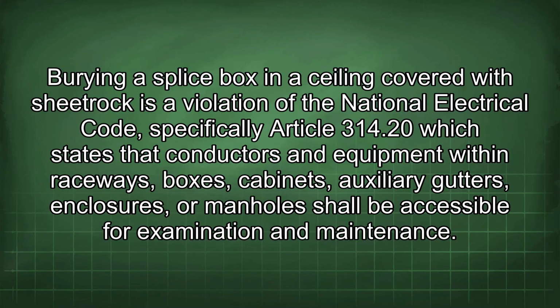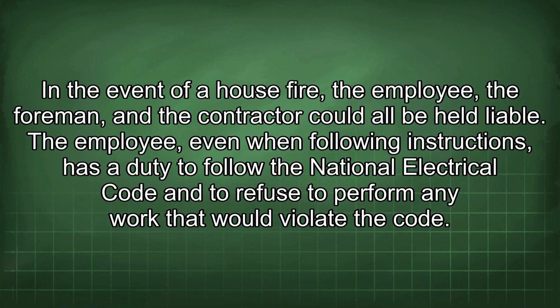Burying a splice box in a ceiling covered with sheetrock is a violation of the National Electrical Code, specifically Article 314.20, which states that conductors and equipment within raceways, boxes, cabinets, auxiliary gutters, enclosures, or manholes shall be accessible for examination and maintenance. In the event of a house fire, the employee, the foreman, and the contractor could all be held liable. The employee, even when following instructions, has a duty to follow the National Electrical Code and to refuse to perform any work that would violate the code.